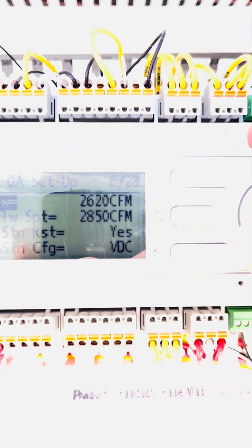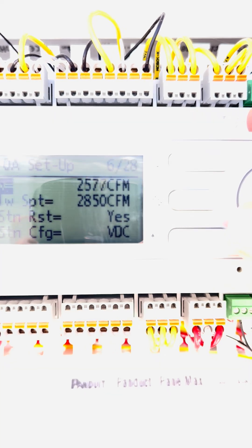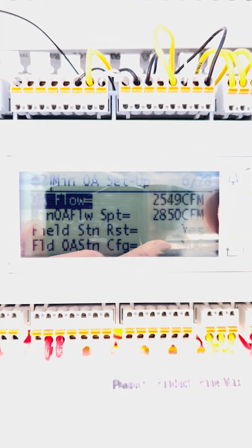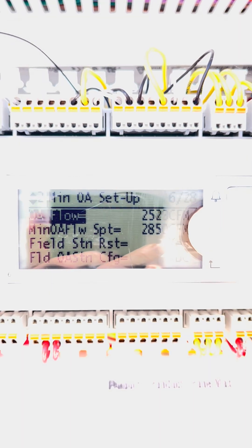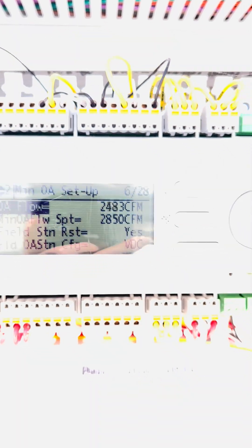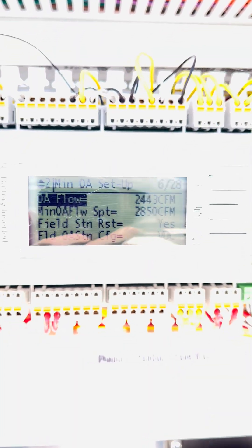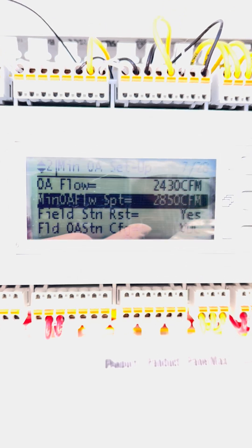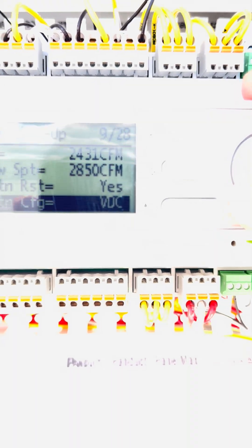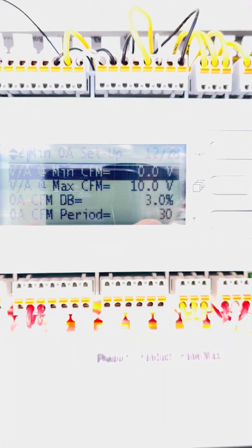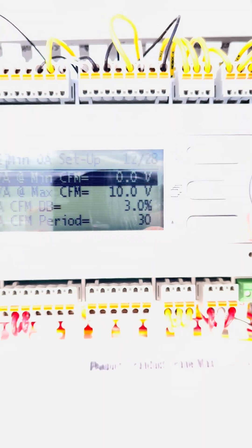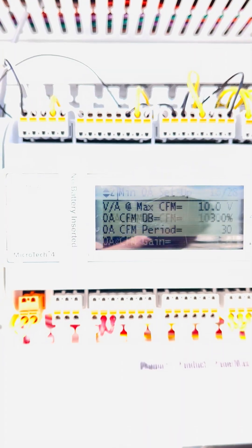Now, what if your outdoor air CFM value doesn't match your min flow or your flow set point? You have to verify below these that it is set up for VDC signal, not mA, and then you have to set what that limit is, 0 volts to 10 volts DC.